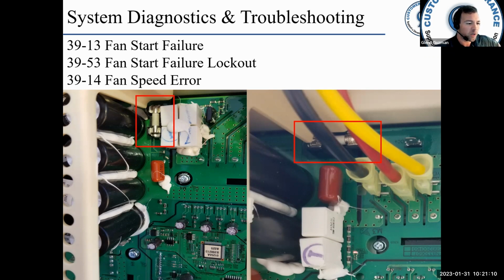You get this fault when the commanded speed is greater than 200 RPM and it differs from the actual speed reported to the VFD by more than 20%. So the fault is also declared when the commanded speed is 0 and the VFD is receiving greater than 80 RPM feedback from the fan motor. Most likely scenario, partial physical blockage of the fan blade, ice buildup, in rare cases, not around here, extreme coil blockage, bearing issues, high resistance to spinning, that sort of thing.